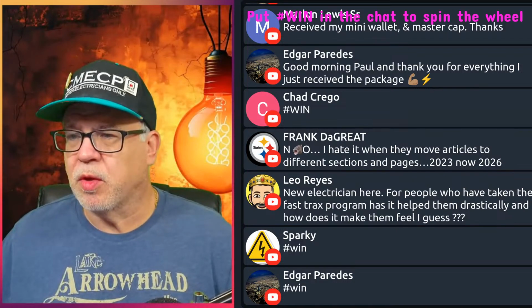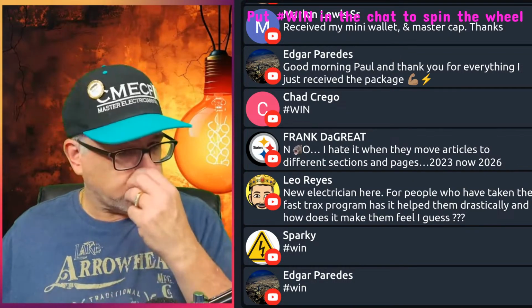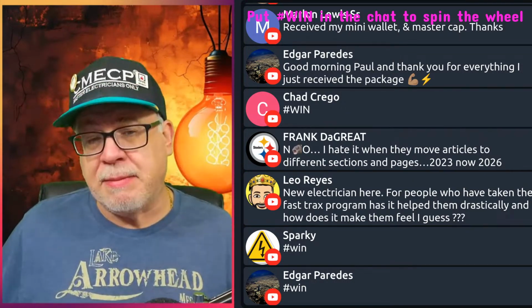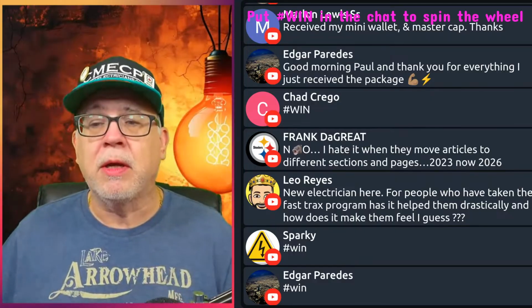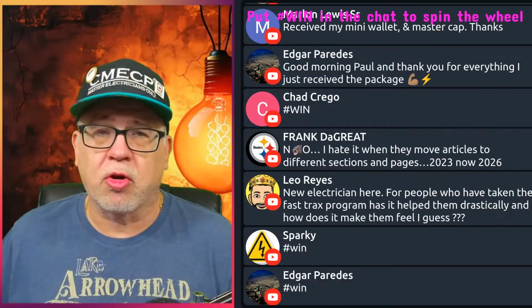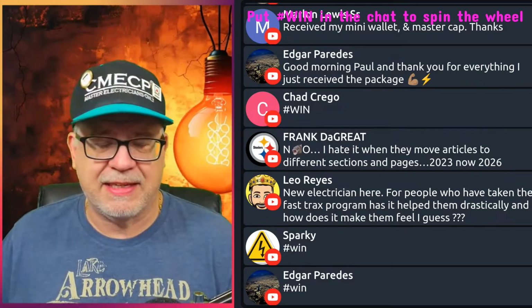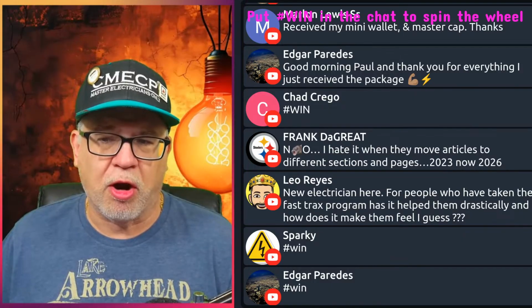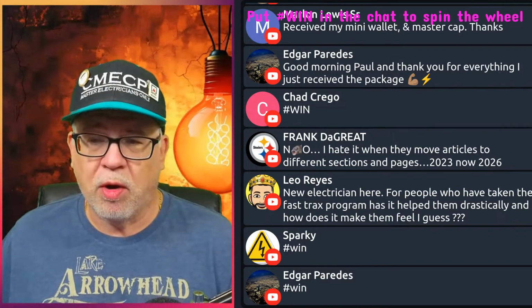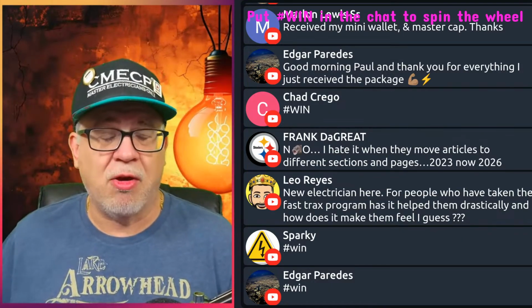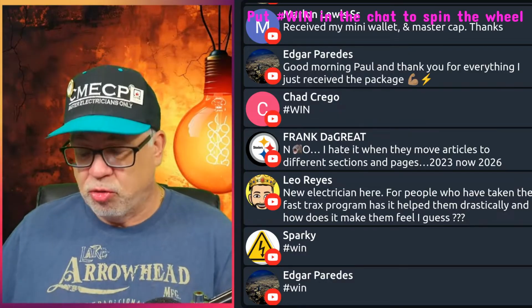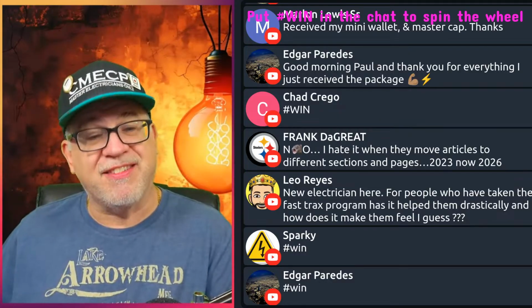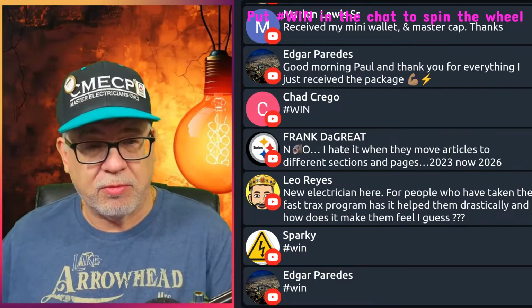All right, let's see the next thing that changed. This may or may not be significant for some people, but we have a change in Article 110.16, and that has to do with the mandatory arc flash labeling. One of the big changes here is it's now going to require you to do a date of the actual assessment, okay?